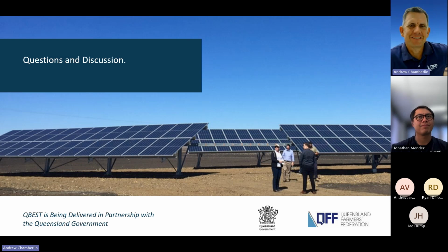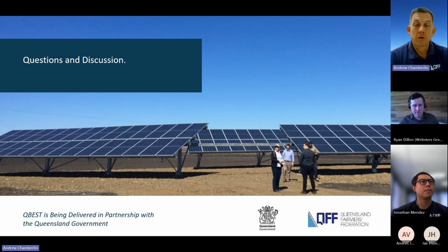That's perfect. And it made me think of another thing, which is the ability to monitor energy consumption on site in real time. Particularly farms that get solar systems can access data in real time from the inverter system, but also by getting a meter put in at the same time, they can see their energy consumption on the same screen as their solar generation, which means they can do what you're talking about, which is try and optimise consumption during solar hours. You can do one meter with all of your energy, but you can get finer and finer grain, so you can put real-time meters on individual pieces of equipment or groups of equipment.